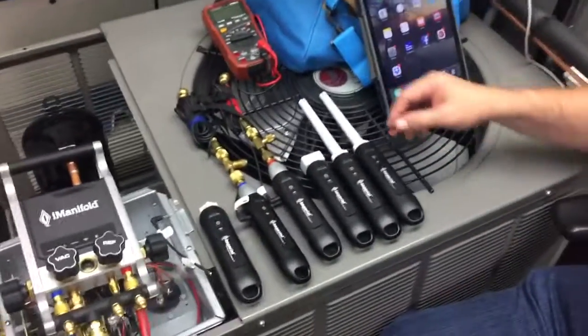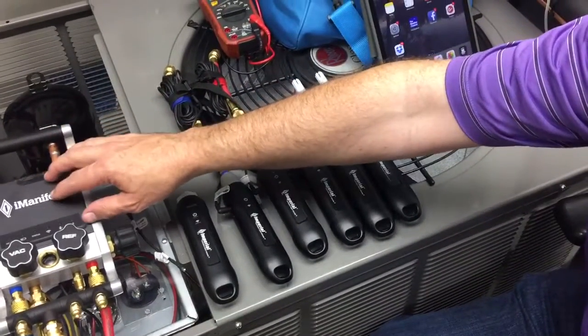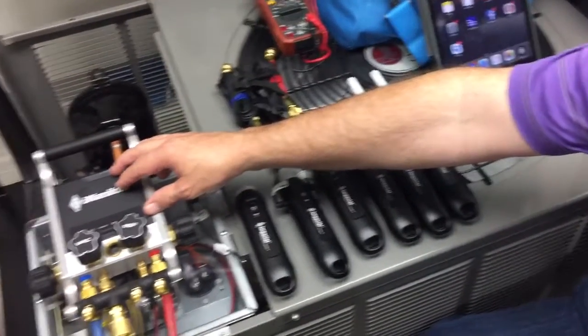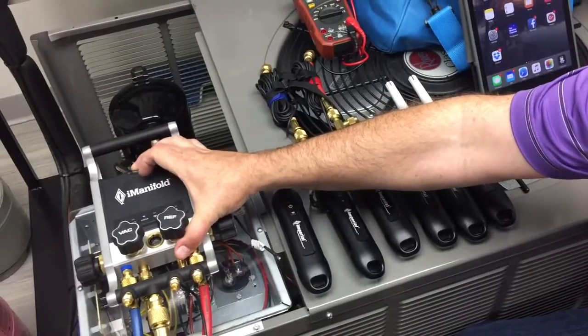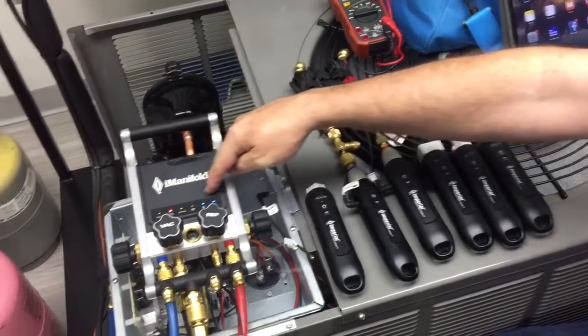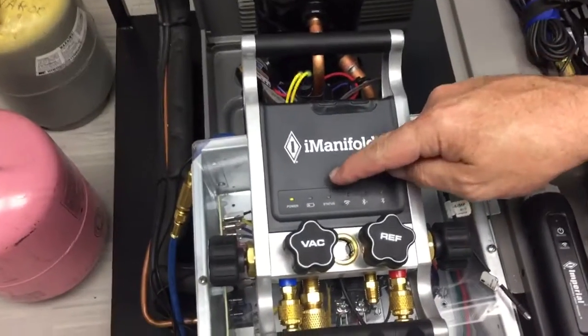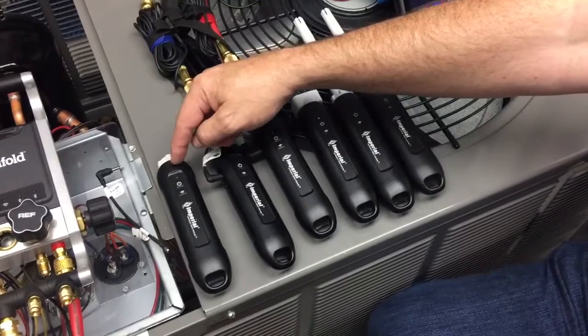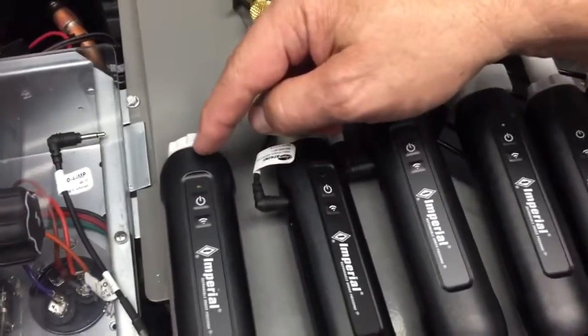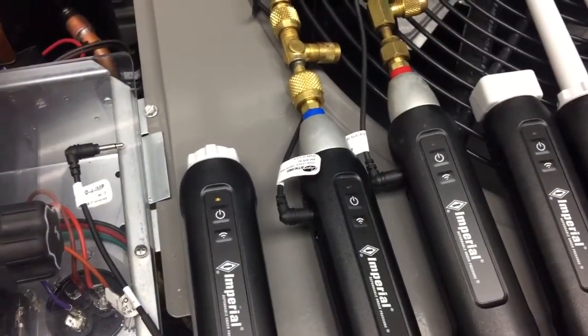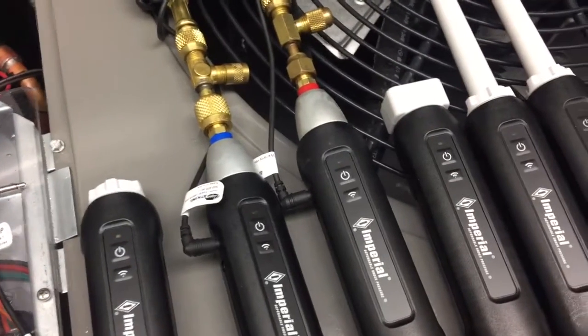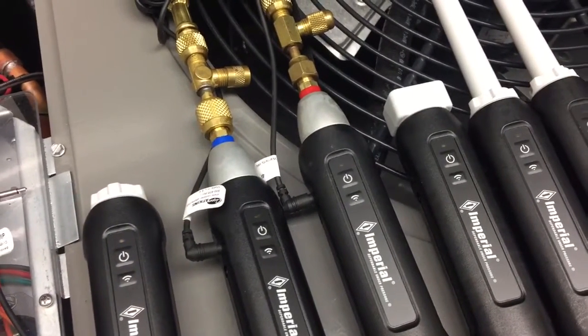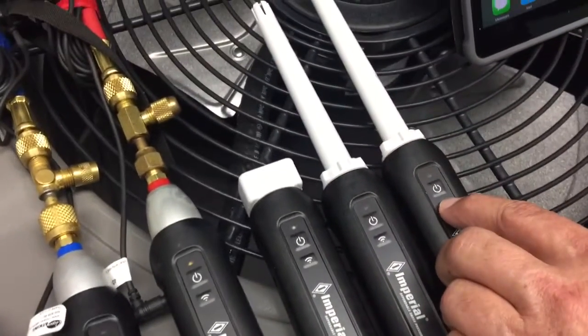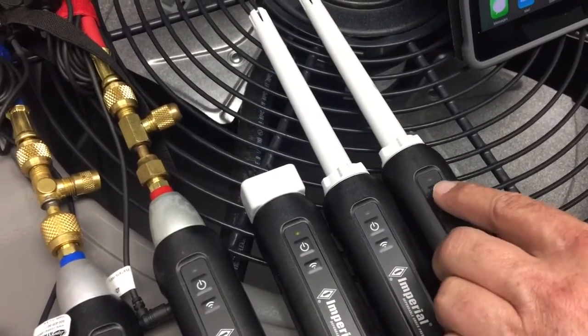Everything here is in pairing mode. Obviously when you first get the iManifold, there are no batteries in it, so you've got to put batteries in. We'll go ahead and turn this on real quick. You'll see the lights come on, everything lights up, and then the status light will just flash. Right now it's in standby. All the wireless probes come with batteries in them, and you can see the lights are doing a double flash. That double flash means they're in pairing mode, and that's the way they all should be out of the box. If for some reason you have one that's constantly flashing, just press and hold the wireless button until it goes into the double flash mode, and everything will be ready to pair.